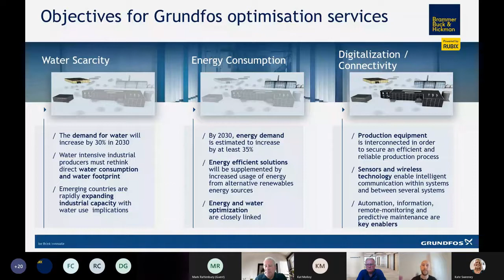But it's not just a case of swapping the pump on a like-for-like basis. It's about looking at the whole control philosophy of the pump. If a pump on site is working at fixed speed 24/7 with no control, can we get to know your systems better? What is the application, what is the process? Can we use a sensor so the pump doesn't work as hard when there's less demand? Then with digitalization, we can feed that back to a system like SCADA or Modbus, so you get real connectivity and a real idea of what the pumps are doing and how much energy is being saved.